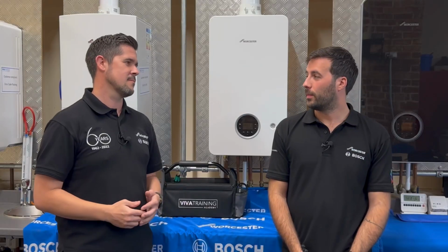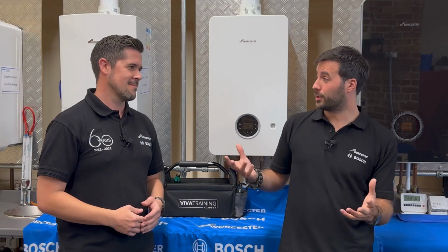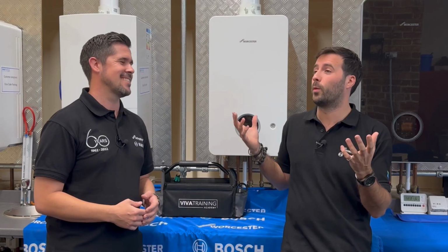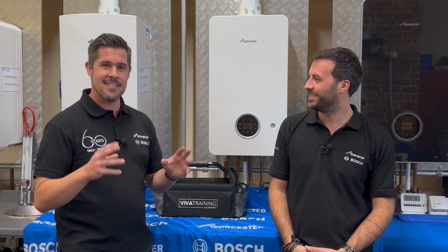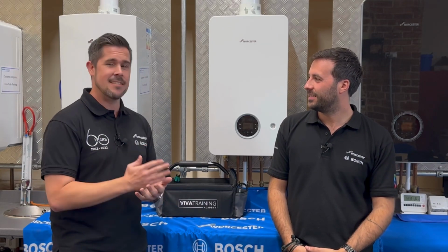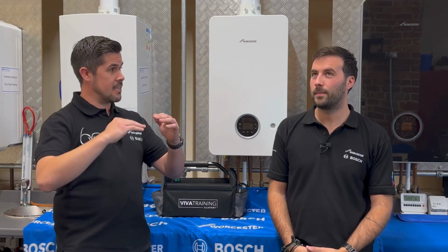All modern equipment, modern boilers are packed full of sensors, and they're normally called NTCs. What on earth is that? So an NTC sensor, Mike, NTC stands for negative temperature coefficient. Basically what that means is that when the temperature in the boiler goes up, the resistance through the component actually comes down, so we see a lower resistance measured through the sensor.